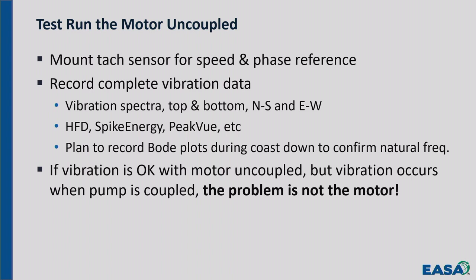Sometimes that's hard to get across to a customer. Or you didn't run the motor without it being coupled to the pump. They just hooked everything up and tested around, and now it vibrates, must be the motor. No, we run the motor first, and it runs smooth, and there's no problems. Then you hook the pump up, and then it vibrates. The problem's not the motor. Okay? Then we can start looking for the real problem and start arguing over whether or not I'm going to pay for it.